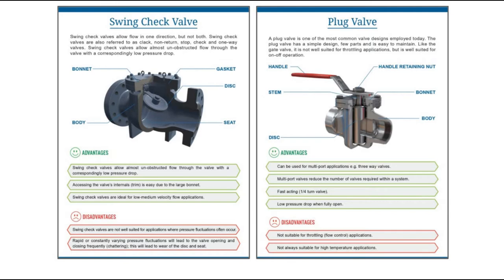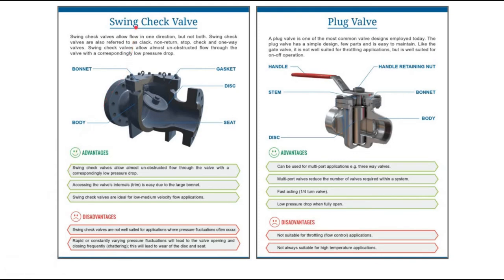Disadvantages of swing check valves: they are not well suited for applications where pressure fluctuations often occur. Rapidly or constantly varying pressure fluctuations will cause the valve to open and close frequently — a situation called chattering — which leads to wear of the disc and seat. So we do not recommend using a swing check valve in pressure-fluctuating situations to avoid damaging the internal components.